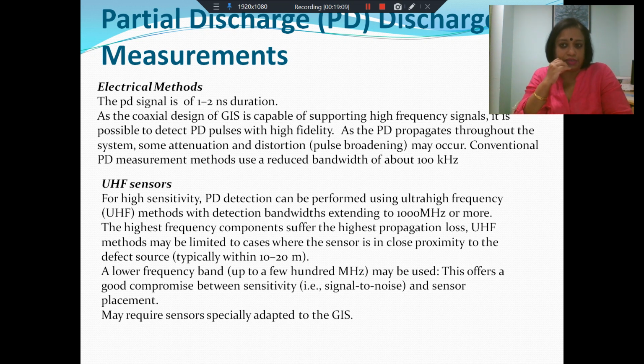Sometimes we don't go to that high frequencies. We still work with UHF, but we use a reduced frequency range, maybe a few hundred megahertz. This offers a good compromise between sensitivity and sensor placement. When we know that we are likely to be at a considerable distance from the source, and do not have access to locations very close to it, we may not go to the highest frequencies, but come to 100 megahertz or somewhere in between. So we are still in the high frequency regime, and we do not expect too much contamination by noise. At the same time, since these are not the highest frequencies, the propagation losses will also be lower. Essentially, we have to decide what frequencies to use and where to place the sensor, and all of this needs engineering judgment. You may also need to use sensors which are specially adapted to the gas insulated substation.